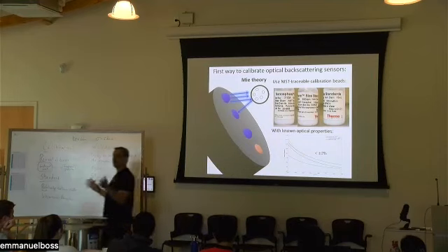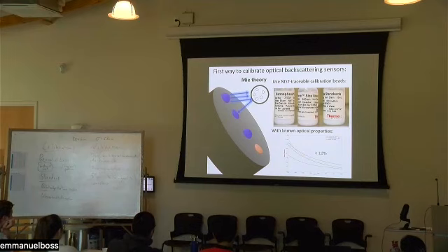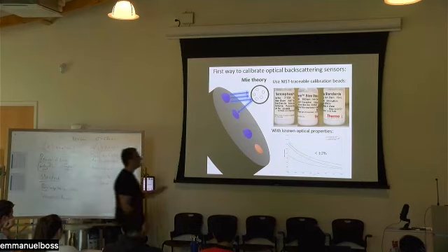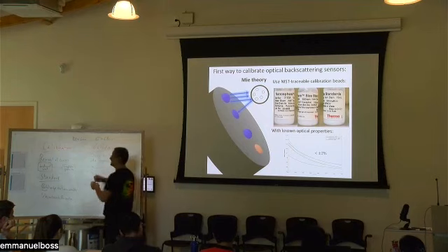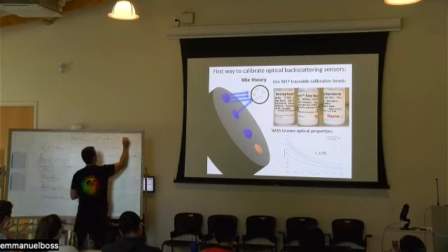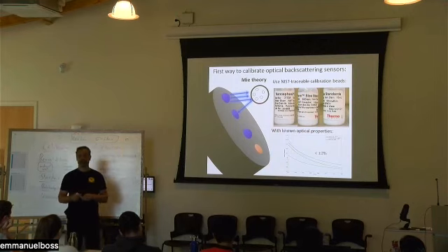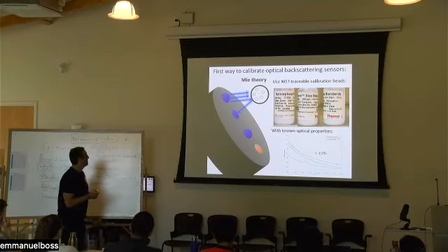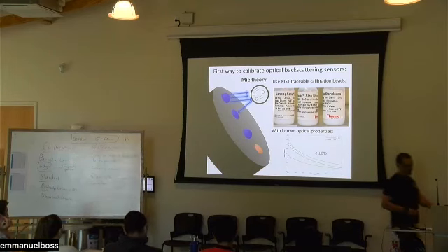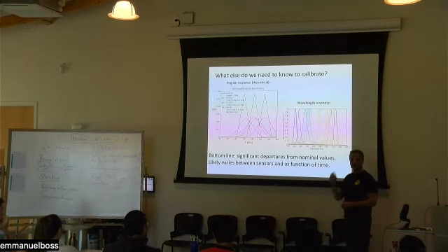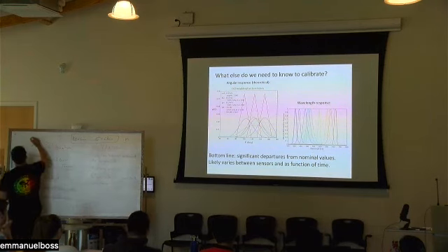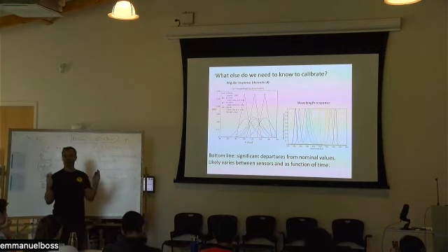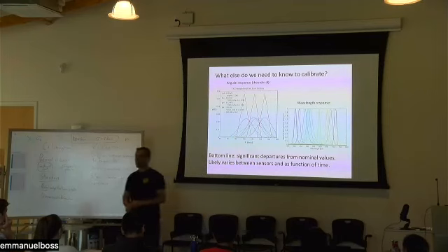there's a variety of indices of refraction published in the literature. There's not a single value everybody agrees on. If you look in the literature, they vary by about 2% in the index of refraction. Remember, for the Mie calculation, I need size, I need this information. I need information about the index of refraction. And what other information do I need? Wavelength. I need a wavelength, so let's look at that. I need to know what's the wavelength and what's the sigma lambda, because these sensors typically are 20 nanometers or more. And then I also need to know what's their angular response. What are the angles?